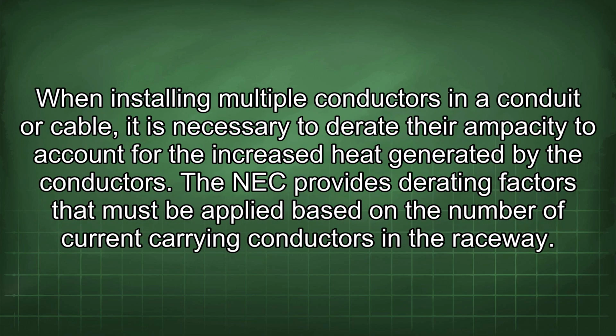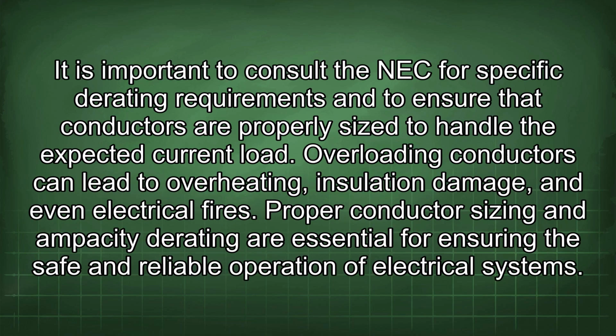When installing multiple conductors in a conduit or cable, it is necessary to derate their ampacity to account for the increased heat generated by the conductors. The NEC provides derating factors that must be applied based on the number of current carrying conductors in the raceway. It is important to consult the NEC for specific derating requirements and to ensure that conductors are properly sized to handle the expected current load. Overloading conductors can lead to overheating, insulation damage, and even electrical fires. Proper conductor sizing and ampacity derating are essential for ensuring the safe and reliable operation of electrical systems.